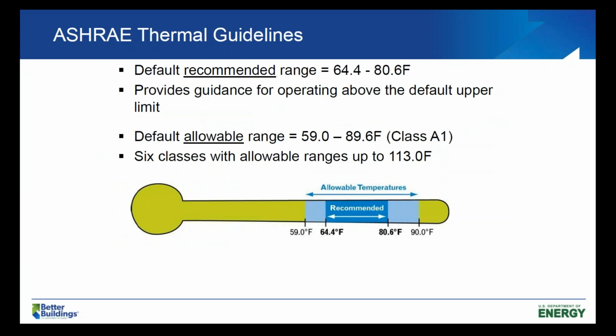So it's important to remember that what matters is the air temperature entering the IT equipment. ASHRAE, the American Society of Heating, Refrigerating, and Air Conditioning Engineers, in collaboration with all the major IT manufacturers, has come up with a set of thermal guidelines with a recommended range and an allowable range. One should always shoot for the recommended range, which is a low of roughly 64 degrees and a high of roughly 81 degrees Fahrenheit, such that the so-called cold aisle should be a comfortable temperature for people, making the hot aisle very warm and uncomfortable. And that's normal operating, and the IT equipment will be perfectly happy there. So keeping in mind that range. Next slide, please.